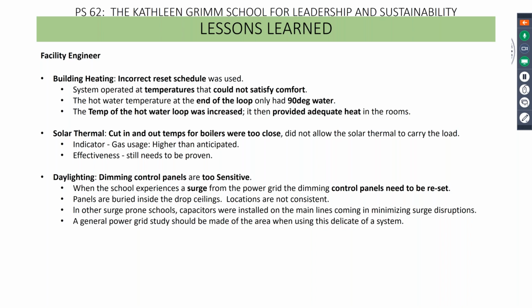We also ended up having issues because the local water supply, since it was towards the end of a run in Staten Island, had quality issues unrelated to the school, just based on the neighborhood, and that storage capacity caused problems. Then having the solar thermal try to keep up with keeping that much hot water at the right level became an issue, which is one of the reasons we said: okay, the solar thermal system, yes, we invested good money in this, however it's causing a lot of problems for the staff to handle and maintain. The glycol was having to be changed more often than it should have. So for those of you who love solar thermal, I'm not saying solar thermal is bad. In our situation it was not something our staff could really handle from a maintenance standpoint, and I think because of the sizing issue, it was a bit of a mismatch.